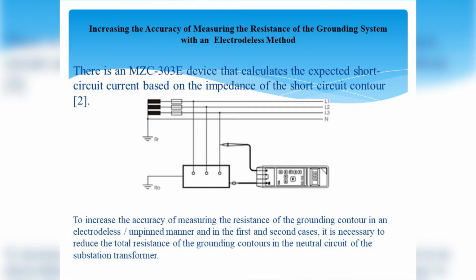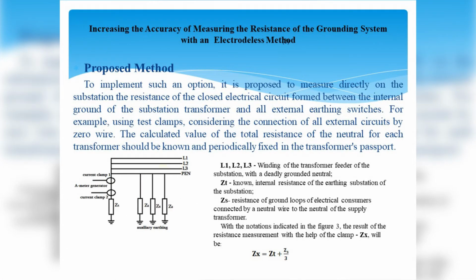To increase the accuracy of measuring the resistance of the grounding contour in an electrodeless unpinned manner in the first and second cases, it is necessary to reduce the total resistance of the grounding contours in the neutral circuit of the substation transformer. For example, performing the neutral ground loop of a substation transformer with a resistance of less than 0.5 ohms. True, this is a very time-consuming and expensive option. There is an option and a simpler way, which consists in determining the resistance of all external ground loops connected to the neutral of the transformer.